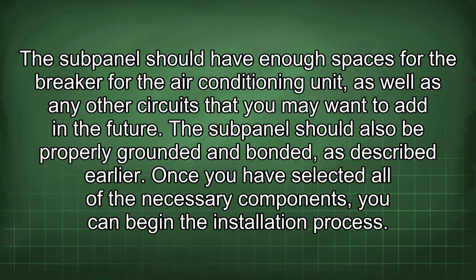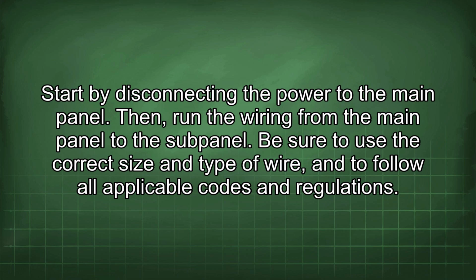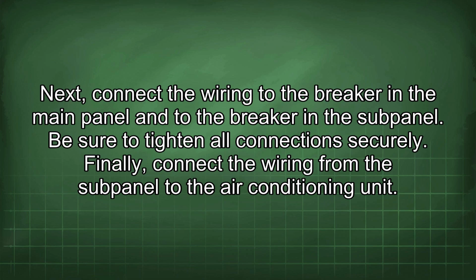Once you have selected all of the necessary components, you can begin the installation process. Start by disconnecting the power to the main panel. Then run the wiring from the main panel to the subpanel. Be sure to use the correct size and type of wire, and to follow all applicable codes and regulations. Next, connect the wiring to the breaker in the main panel and to the breaker in the subpanel. Be sure to tighten all connections securely.